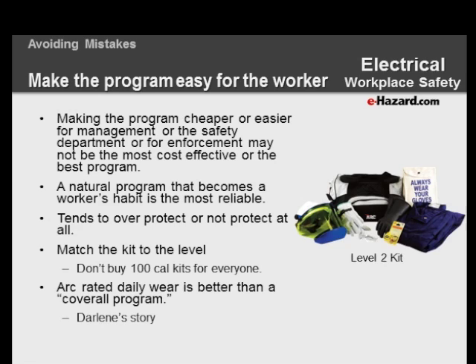If this company had been in a full uniform, that they just went out in the right gear for the basic level of flame resistance and arc-rated low-level gear all day long, and then put on a coverall for different things, and then put on a flash suit when they needed, this person would have been much better protected and she wouldn't have gotten burned hardly at all, if not any at all.